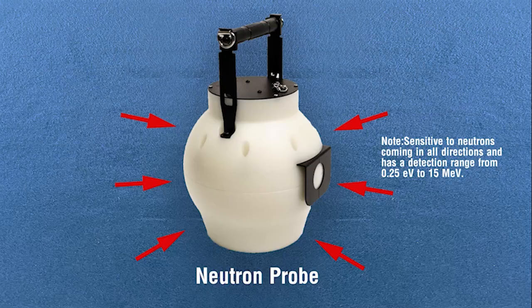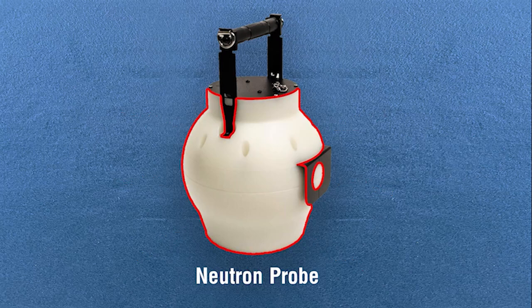The neutron probe is sensitive to neutrons coming in all directions and has a detection range from 0.25 eV to 15 megaelectron volts. It is surrounded by high-density polyethylene, a special plastic that is installed around the detector in order to efficiently slow high-energy neutrons to a detectable level. Neutron radiation is detected with solid-state semiconductors. The probe can detect radiation from any direction, but has a wall plate for holding the probe against a wall or flat surface.